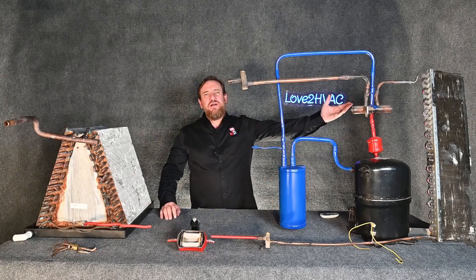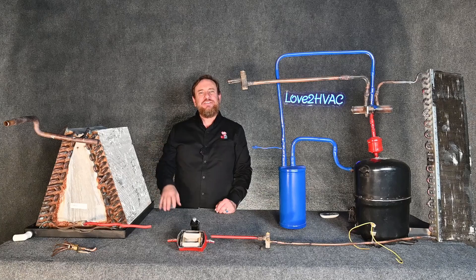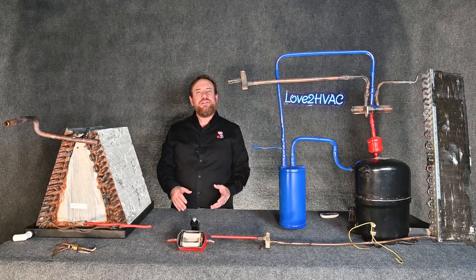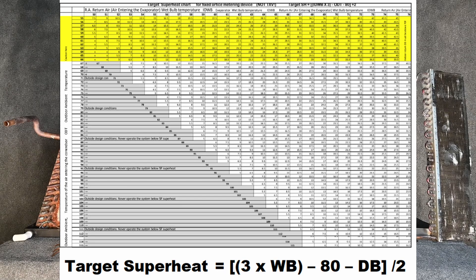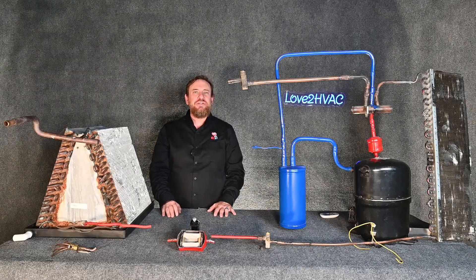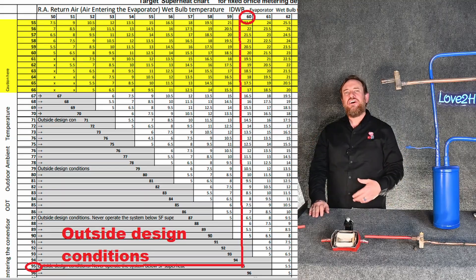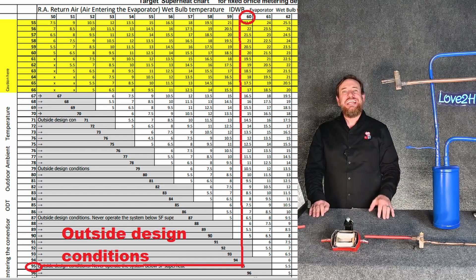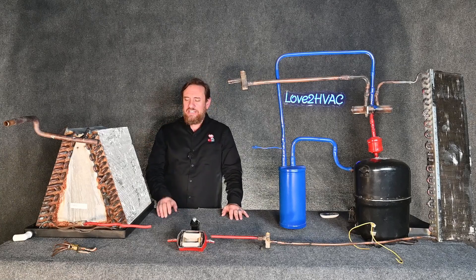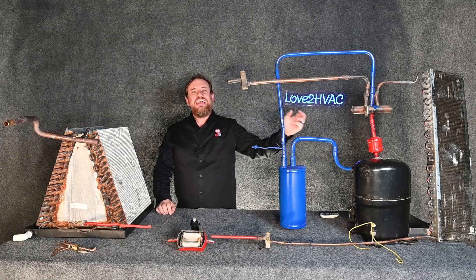In AC mode as the outdoor temperature rises we have more pressure pushing more refrigerant through that metering device, which affects how much liquid refrigerant is in the evaporator. The indoor temperature and humidity also affect how fast that refrigerant boils from liquid to vapor inside the evaporator coil. That's why in summer we need the target superheat chart with outdoor dry bulb and indoor wet bulb. For example, on a 95-degree outdoor day at 73 degrees inside at 50% relative humidity, the target superheat can calculate to below zero, meaning under those conditions a correctly operating system would flood the evaporator with liquid refrigerant.